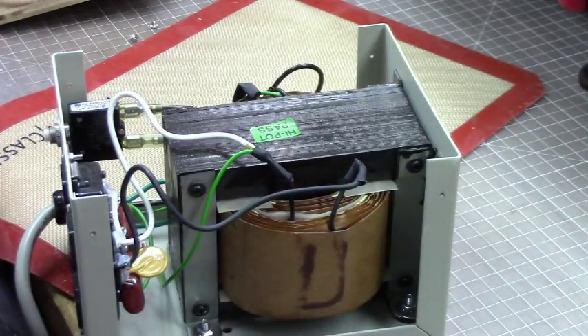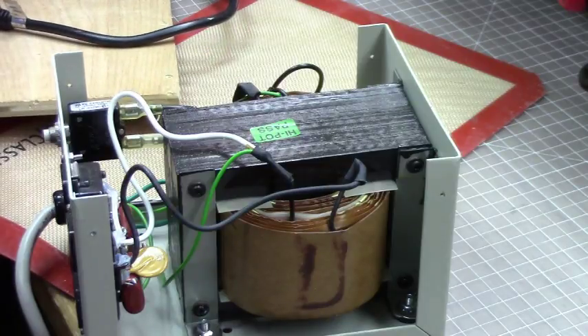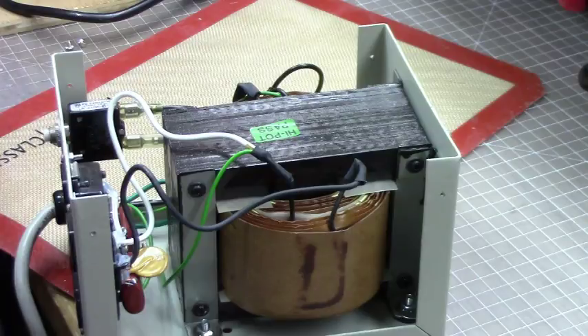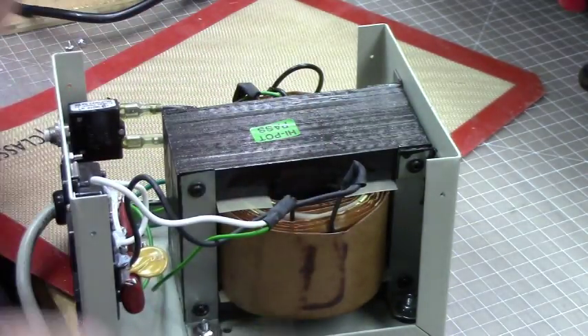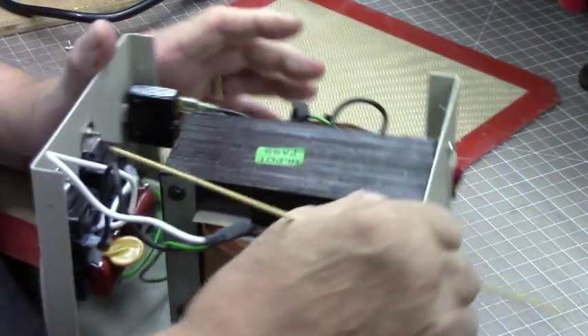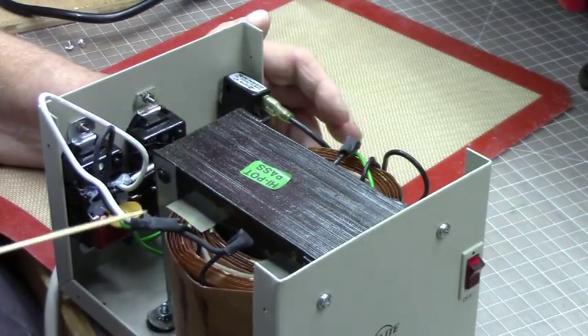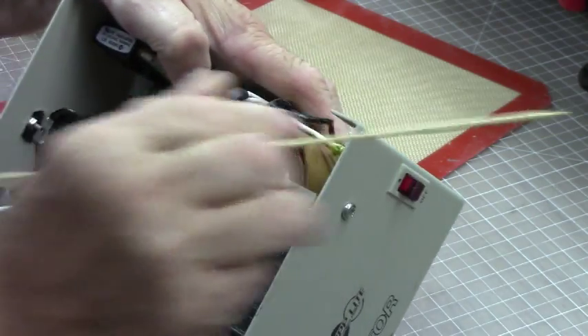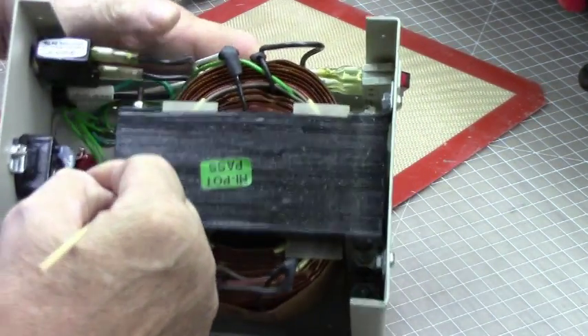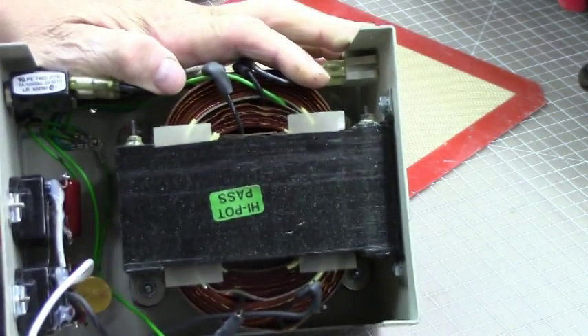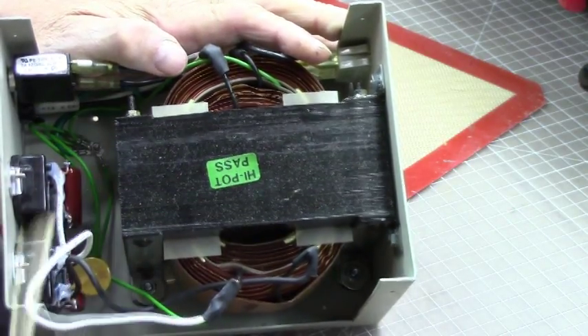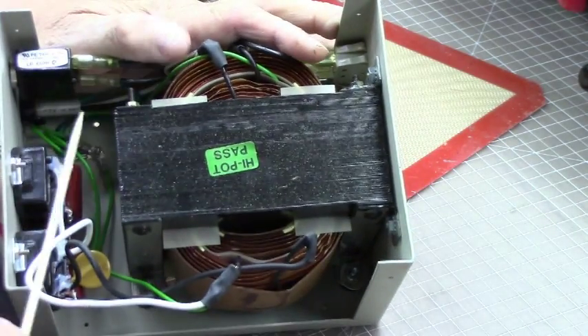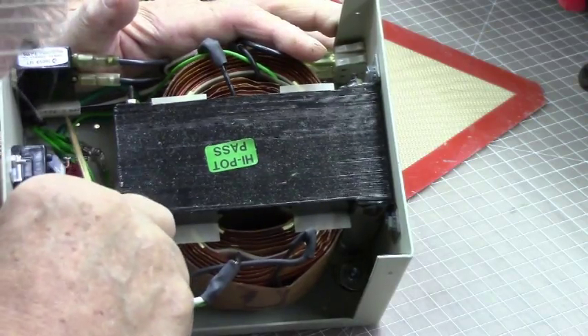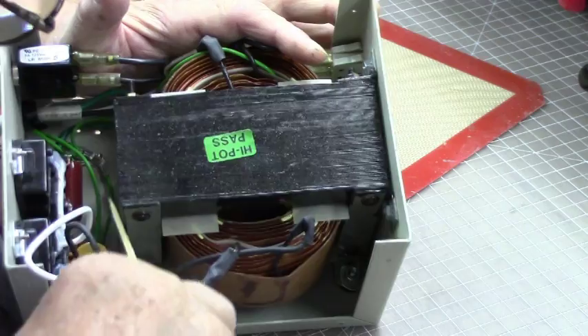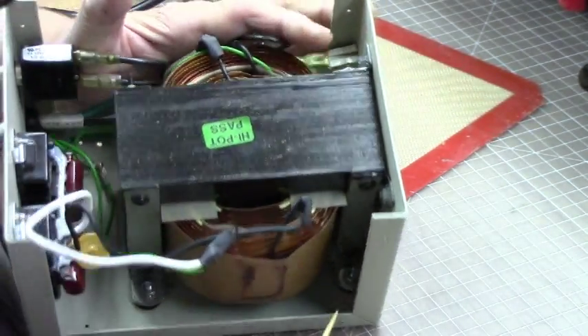Now, the reason this isn't a true isolation transformer is a true isolation transformer is completely isolated from the mains. This one, although the hot side and the neutral side are insulated from the mains, you'll notice that the ground, I don't know, can you see that? The ground in there is connected to the outlets, to the 3-prong receptacle here, and actually there's separate wires into the receptacles.